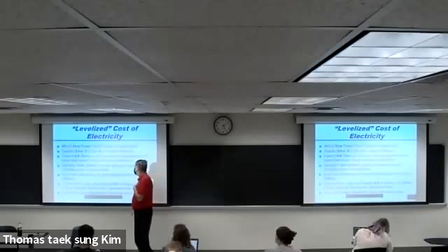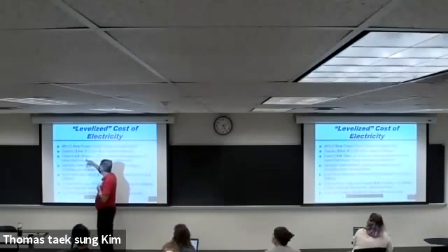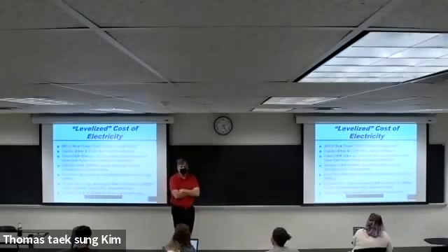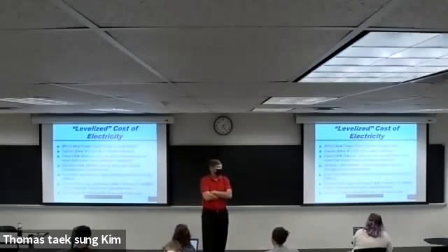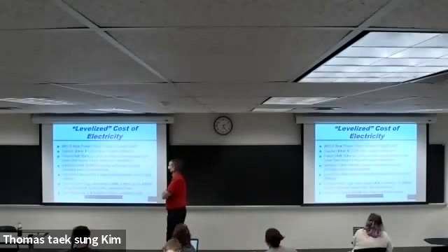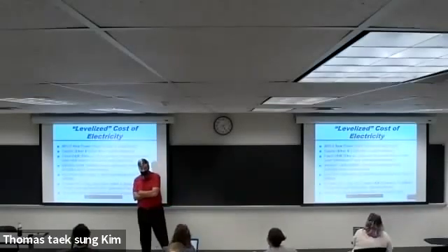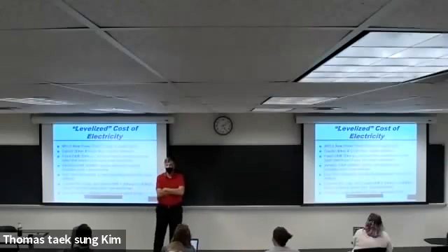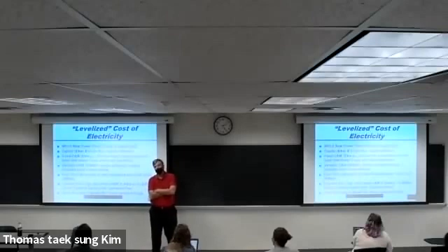So if we use the term $10 a kilowatt year, that would mean that for a 500 megawatt plant, you would spend in fixed operating and maintenance costs $10 a kilowatt times 500 megawatts, which is 500,000 kilowatts. So think of 10 times 500,000, that's $5 million.